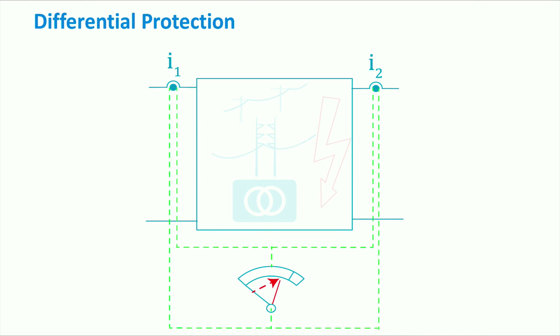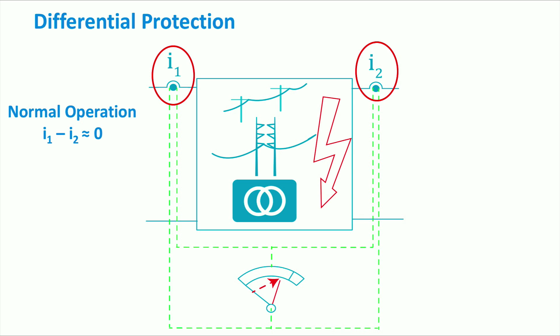The equipment could be a transformer, a distribution or transmission line, etc. This method consists of comparing the input and output current of the equipment. During normal operation, the difference between the two values is very low, which is due to the internal power losses in the equipment.